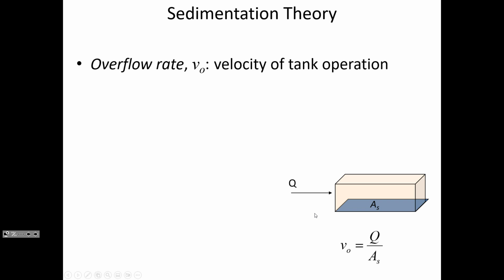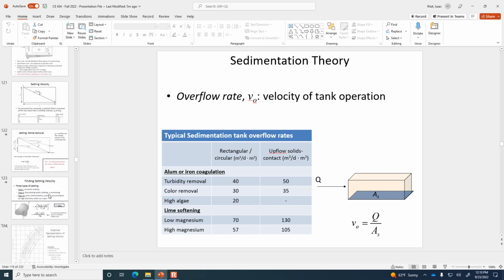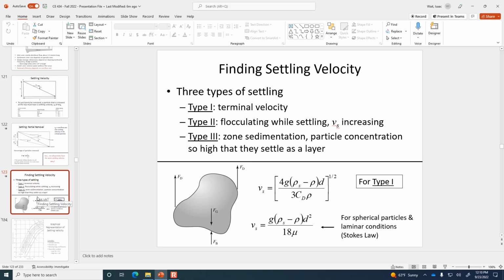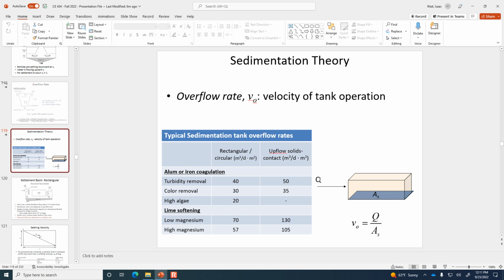And at first that's kind of counterintuitive because think about what these particles are doing during settling. They're falling downward. So you'd think if you give the particles twice as long to settle, maybe that would improve your settling performance. What I'm telling you is it doesn't change the settling performance at all. That the settling performance only depends on the flow rate and the bottom surface area.